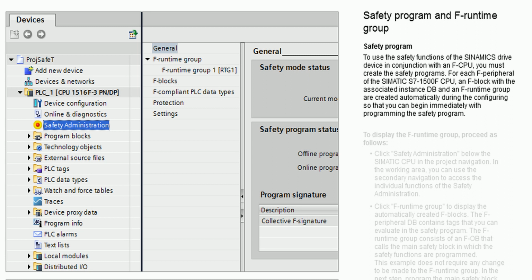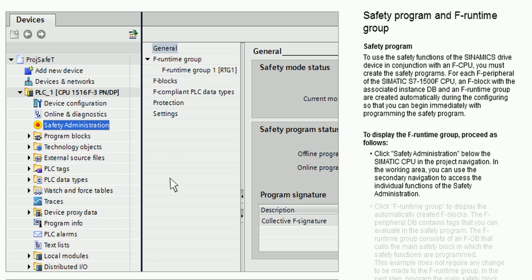Safety Program. To use the safety functions of the SINAMICS drive device in conjunction with an F-CPU, you must create the safety programs. For each F peripheral of the SIMATIC S7-1500 F-CPU, an F block with the associated instance DB and an F runtime group are created automatically during the configuring so that you can begin immediately with programming the safety program. To display the F runtime group, proceed as follows. Click Safety Administration below the SIMATIC CPU in the project navigation.